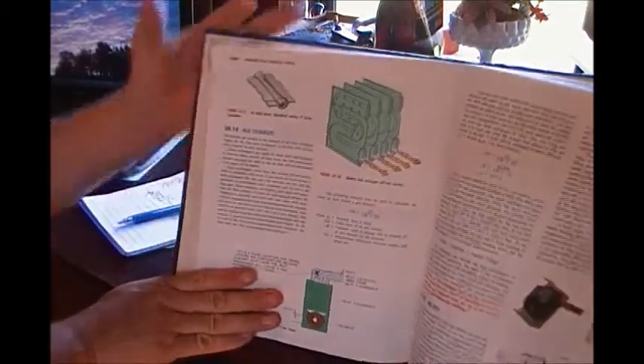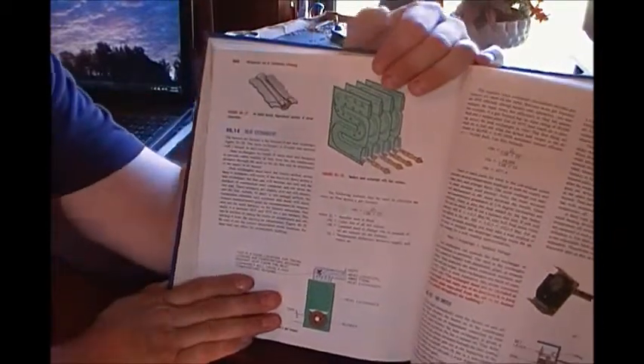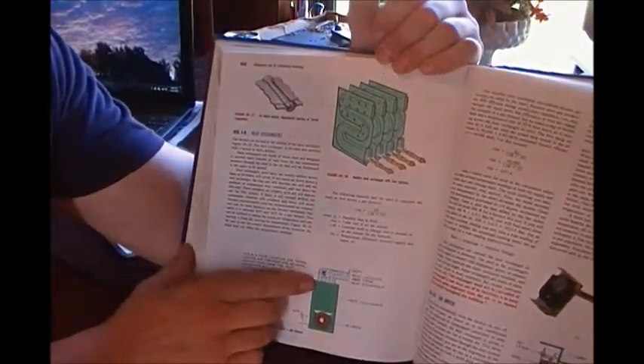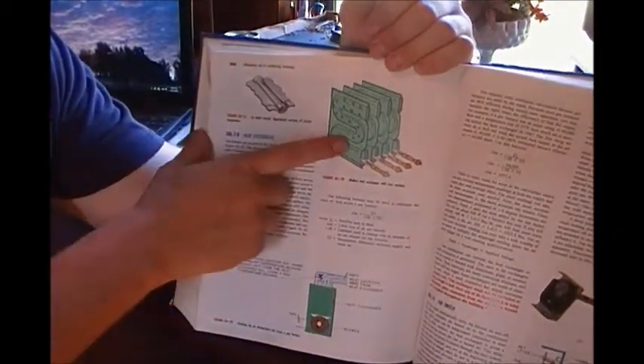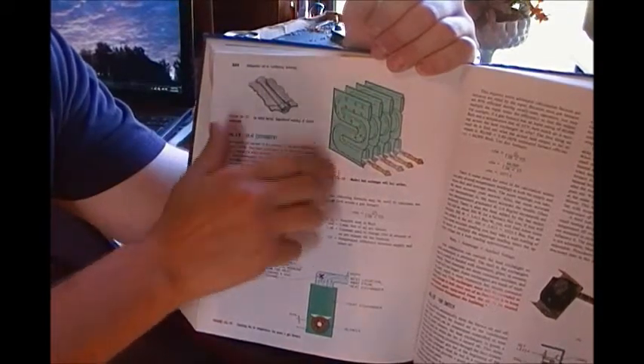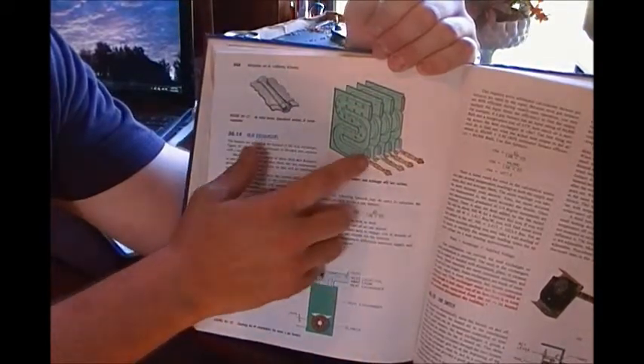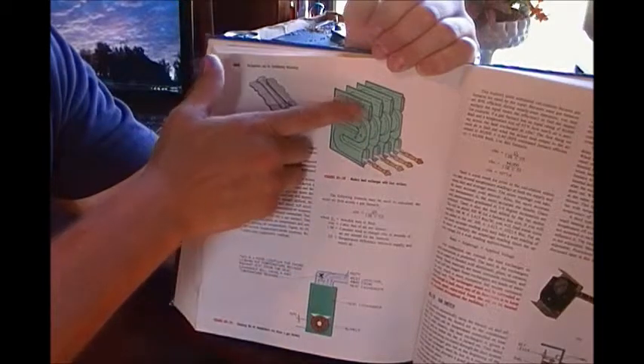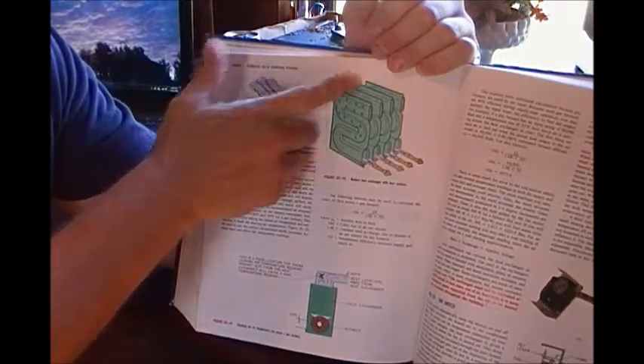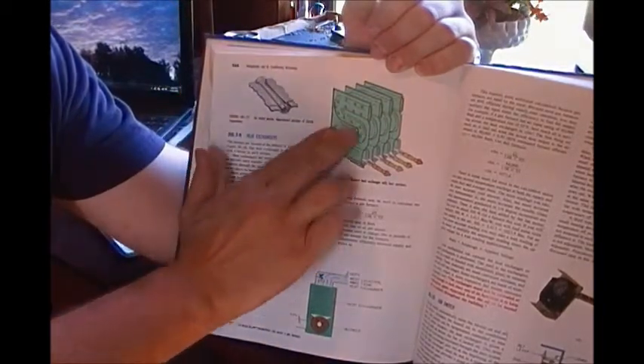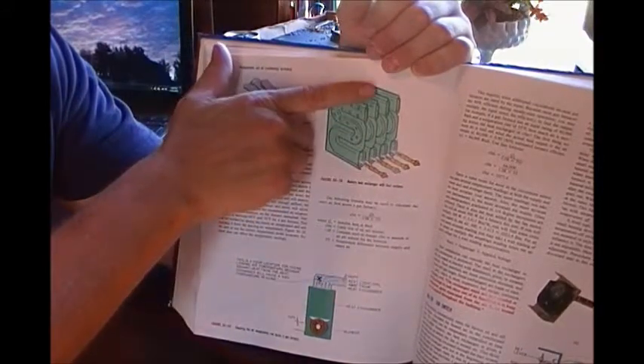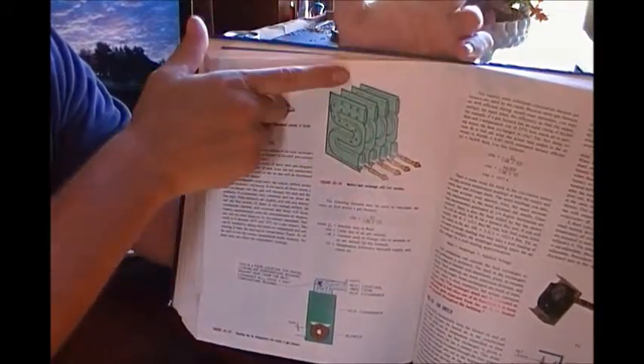So for efficiency, and because you don't want to send too much across that exchanger, if you overheat the exchanger, it will crack, and then there'll be holes in it. What happens is gas goes in through the bottom, goes around this, and comes out up here and goes out the flue pipe. And then the air is blown up underneath it, coming out the top and going out your plenum on the top of here.